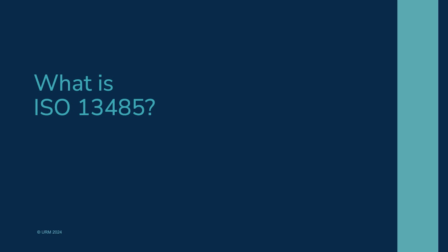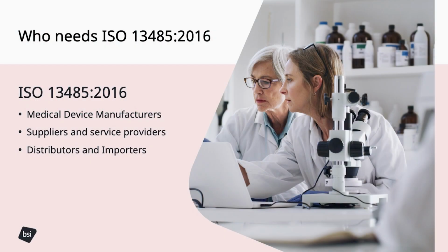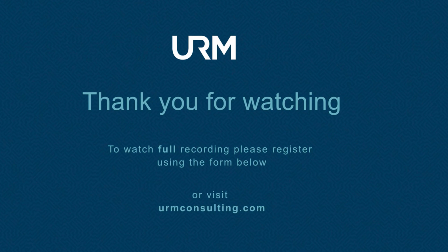So let me just step back, and can we start with what is ISO 13485? Okay, yeah, so ISO 13485, or 13485 as we sometimes call it for ease of use, is an international standard. It's been officially adopted now for a number of years, since 2016, and it is specifically intended for the medical device industry. So normally when I first speak to a client, I say it's a bit like 9001, but it's specifically aimed at the medical device industry.